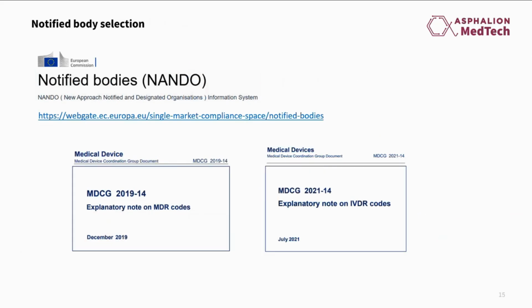I want to make a specific focus on this part because, as said, you can freely choose the notified bodies that work better for you. But I need to add a requisite: the notified bodies need to be designated as having the expertise to assess your device in particular. Bear in mind that the medical device sector is really varied. As I said, there could be different typologies, a wide range of products governed by the same regulation. Therefore, not all notified bodies are designated for having the capacity to assess all types of devices. So first of all, you need to review what they call the MDR code or the IVDR code. This is the code assessing the expertise of a notified body, and you should choose specifically the notified body designated for assessing your type of device.